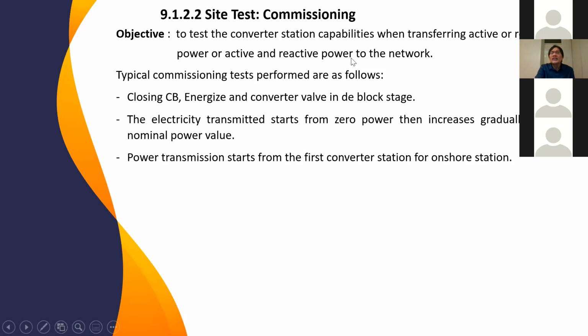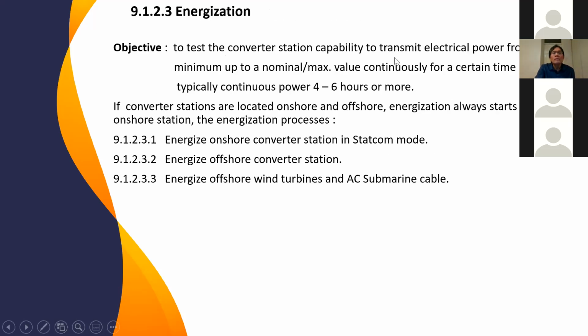Commissioning tests when transferring active power, or reactive power, or active and reactive power to the network. So for commissioning, it depends on the availability of the power. Sometimes the test for commissioning is only to transfer active or reactive power. For energization, we test the converter station's capability to transmit electrical power from minimum until maximum or nominal power. Once again, it depends on the availability of power.